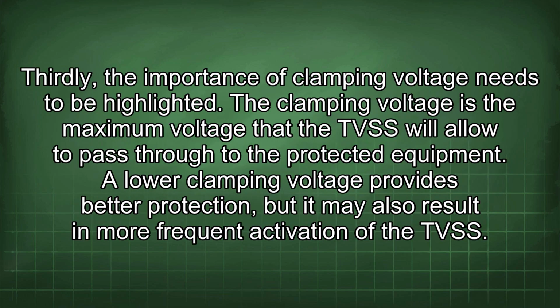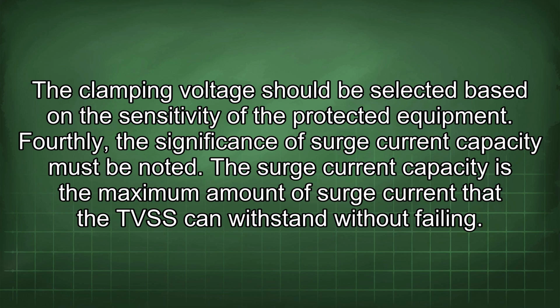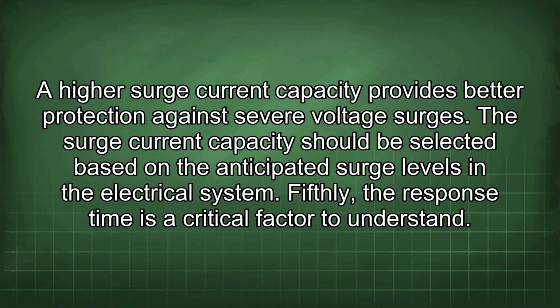Thirdly, the importance of clamping voltage needs to be highlighted. The clamping voltage is the maximum voltage that the TVSS will allow to pass through to the protected equipment. A low clamping voltage provides better protection, but it may also result in more frequent activation of the TVSS. The clamping voltage should be selected based on the sensitivity of the protected equipment. Fourthly, the significance of surge current capacity must be noted. The surge current capacity is the maximum amount of surge current that the TVSS can withstand without failing. A higher surge current capacity provides better protection against severe voltage surges. The surge current capacity should be selected based on the anticipated surge levels in the electrical system.